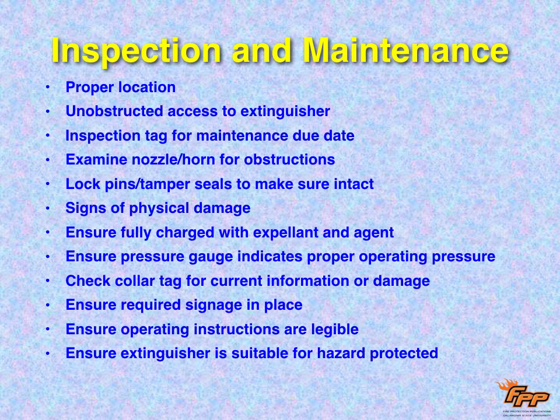Last slide, oh my gosh, I'm sorry this took just over an hour. Proper location has to be inspected on a regular basis, that the extinguisher is not blocked from access, that all the parts are there, the inspection tag, the nozzle, the horn, the lock pin, that it's not damaged, that it's got the right product in it. Look at the pressure gauge, make sure it's at the proper pressure, and ensure it's all properly hung, that the signage is there, a sign above it with extinguisher and an arrow facing down, unless it's very, very visible. And all of these things need to be checked on a monthly and an annual basis.